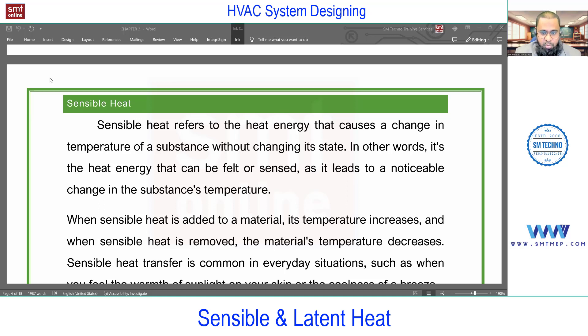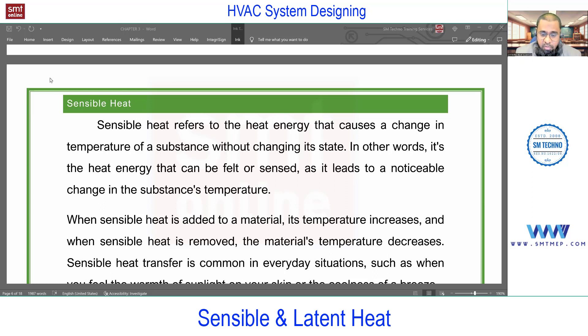When we deal with heat gain through these different sources, you must know that heat gain is either only sensible or sensible plus latent. According to that we have a list. For example, heat gain through wall is only sensible. Similarly, heat gain through ventilation is sensible plus latent because moisture is also involved. Heat gain through people is also sensible plus latent.